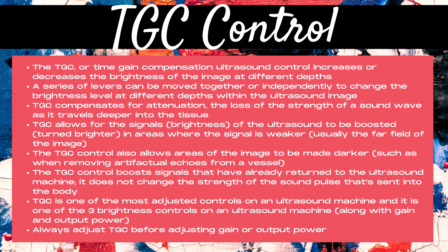The TGC control boosts signals that have already returned to the ultrasound machine, and it does not change the strength of the sound pulse sent into the body like the output power control does.